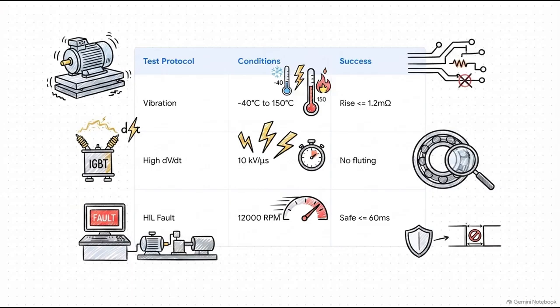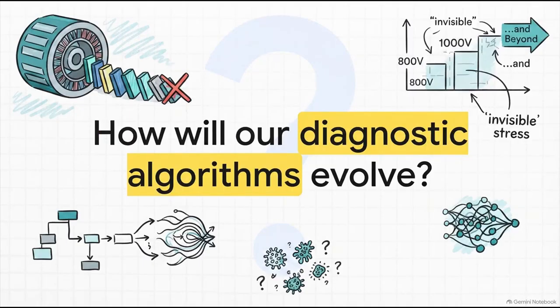Then they get hammered with 1,000 hours of that 10 kilovolt per microsecond high voltage stress at high temps, just to prove they can make it without a single microcrater of bearing fluting. Lastly, on the hardware in the loop test bench, engineers literally inject critical faults on purpose while the motor is screaming at 12,000 RPM. They do this to prove the safety system still catches the fault within that tiny 60 millisecond window. It's just a massive triumph of modern engineering.